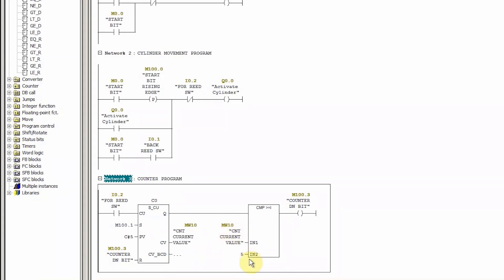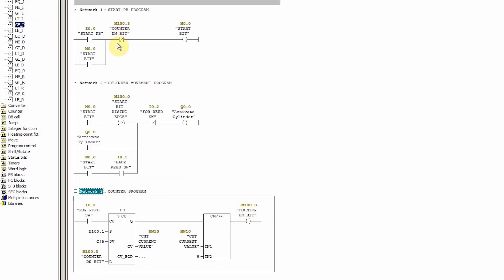A comparator instruction — greater than or equal to — compares memory word MW10 with the value 5. Whenever the counter value reaches 5 or greater, it turns on the counter done bit M100.3. This bit does two things: it resets the counter value back to zero via the reset input, and through a normally closed contact it unlatches the start bit M0.0, stopping the cylinder movement and deactivating the cylinder.